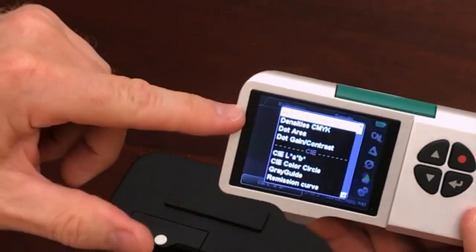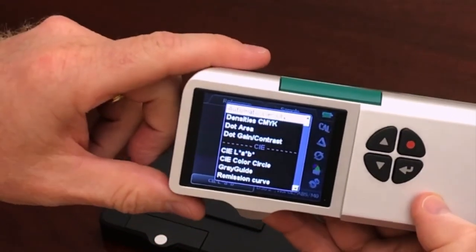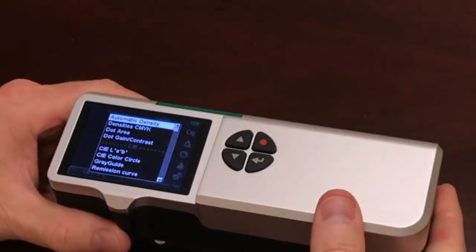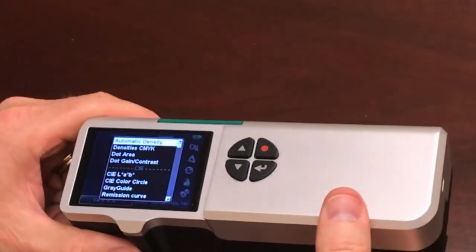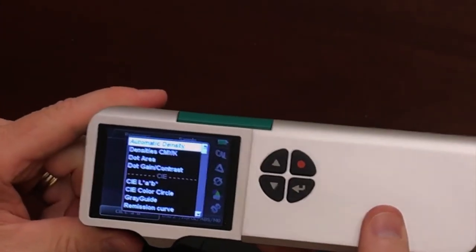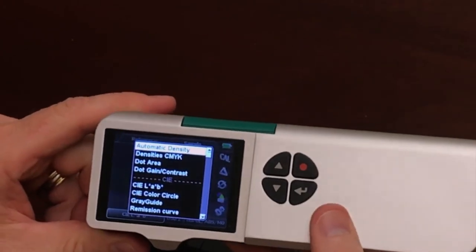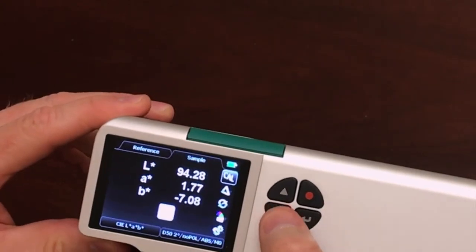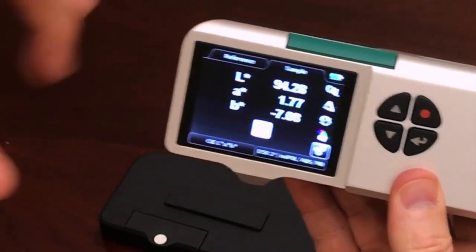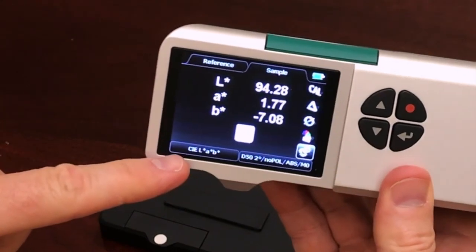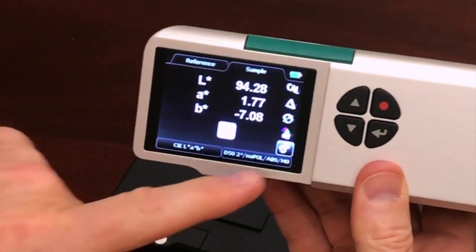If you want to lock the device so that this list of features cannot be changed, you can set it up on the device the way I just did. You can also connect the instrument to your PC where you have the Spectra Connect software installed, open up the Spectra Connect software, and actually disable the settings menu on the instrument itself. That means your press operators are going to have just the features that are in this menu.